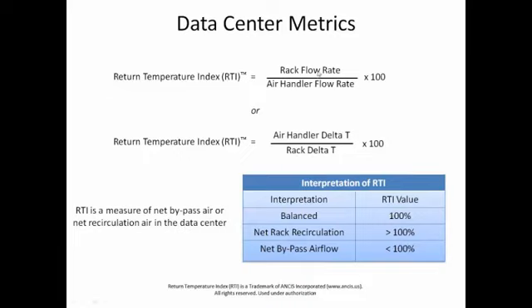But if the rack is getting more air than it needs, this portion is going to decline, and therefore you're going to have net bypass airflow. The air is going to be going around the rack, not through it, and back to the air handler. A problem there is twofold. One, it's a waste of energy. Number two, it reduces the return air temperatures, and therefore the efficiency of the heat rejection system itself. So that's not a good thing.